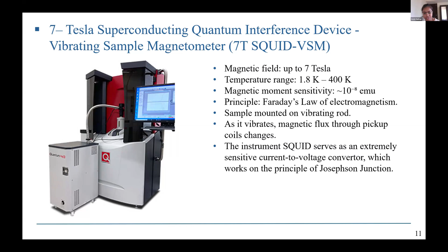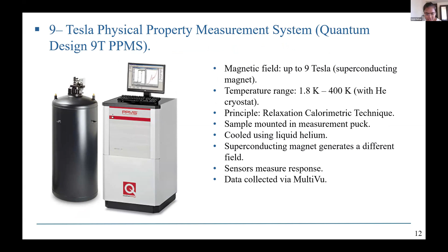Similarly, for the 9 Tesla PPMS, the magnetic field goes up to 9 Tesla. Temperature range is 1.8 Kelvin to 400 Kelvin. The principle of this system is relaxation calorimetry. The sample is first mounted on a measurement puck. The system is cooled with liquid helium, and the superconducting magnet generates the different fields. The sensors also measure the responses, and they are collected in the MultiVu software.